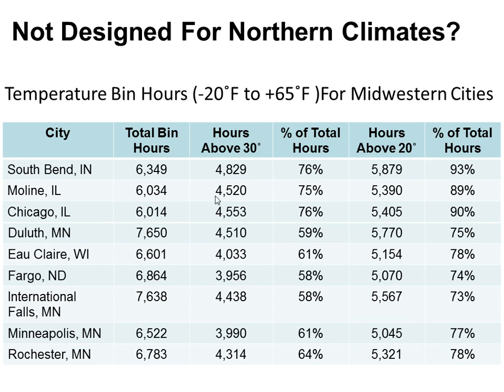the entire year. So the second column here, where it says above 30 hours, that's how many hours are between 30 and 65 degrees outside. So what are our heating hours throughout the year that are above 30 degrees? It's 4,500 hours. More than half of the entire year and 3/4 of the heating year, we have temperatures above 30 degrees, which are a prime opportunity for heat pumps, even regular heat pumps.